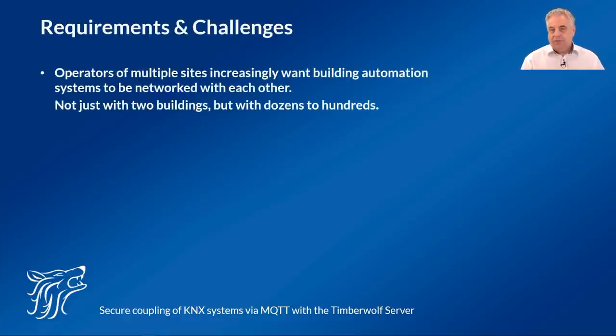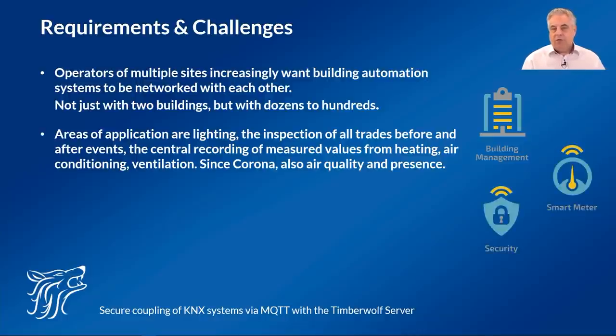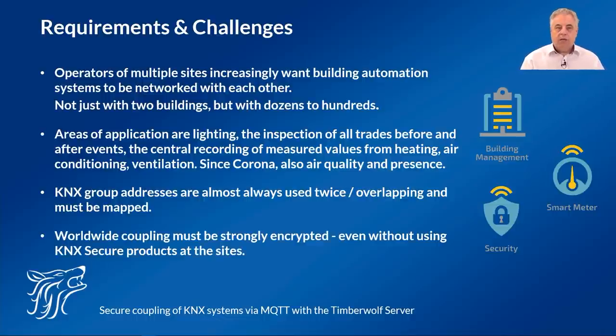Operators of several buildings increasingly want their respective automations to be linked to each other — not just between two buildings but between many, sometimes dozens to hundreds of buildings. Often it is about the management of lighting, the testing of all trades before and after events, but very often also about the central recording of measured values from heating, air conditioning, and ventilation. Since Corona, air quality and evaluation of presence detectors also present a challenge. Group addresses are used twice or overlapping and must be mapped for each building. Worldwide coupling must be possible via the internet and must be encrypted, even if the locations are not equipped with KNX Secure products.